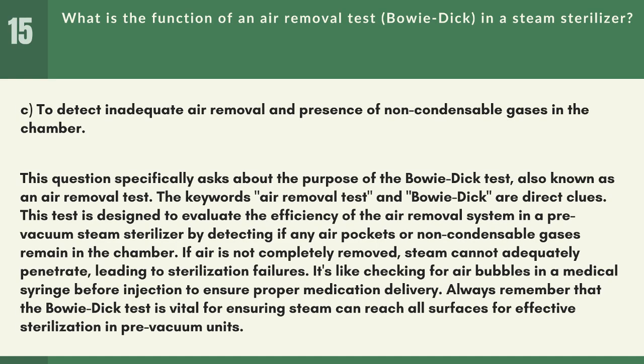Answer C. To detect inadequate air removal and presence of non-condensable gases in the chamber. This question specifically asks about the purpose of the Bowie-Dick test, also known as an air removal test. The keywords air removal test and Bowie-Dick are direct clues. This test is designed to evaluate the efficiency of the air removal system in a pre-vacuum steam sterilizer by detecting if any air pockets or non-condensable gases remain in the chamber.